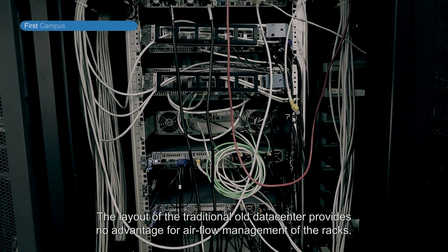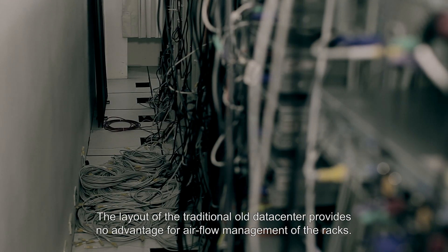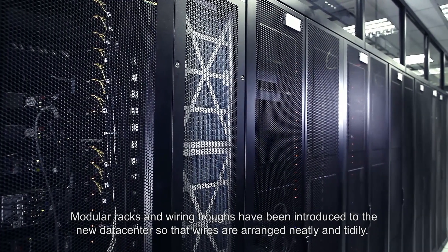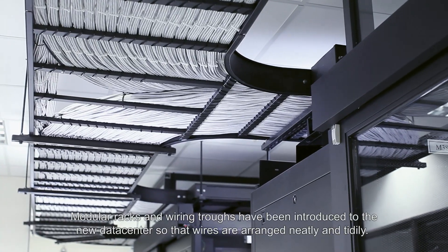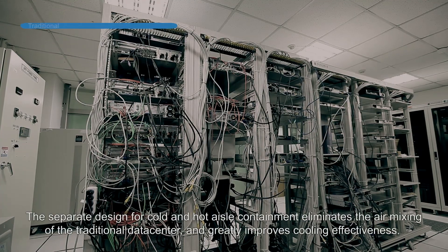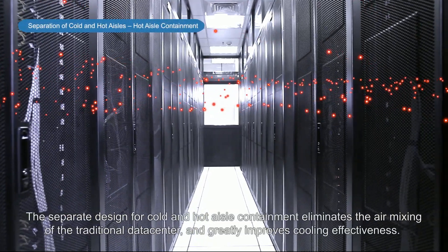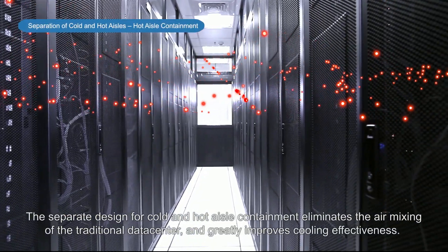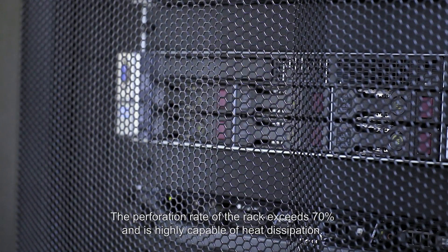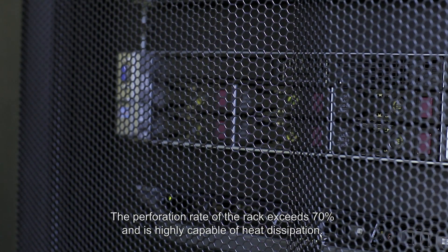The layout of the traditional old data center provides no advantage for air flow management of the racks. Modular racks and wiring troughs have been introduced to the new data center so that wires are arranged neatly and tidily. The separate design for cold and hot aisle containment eliminates the air mixing of the traditional data center and greatly improves cooling effectiveness. The perforation rate of the rack exceeds 70% and is highly capable of heat dissipation.